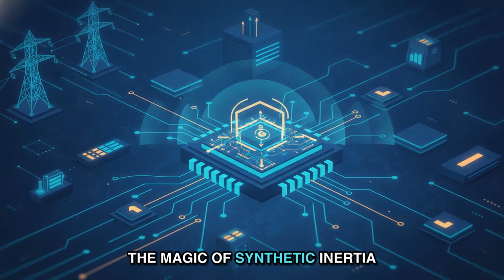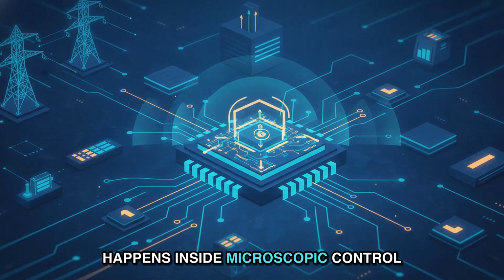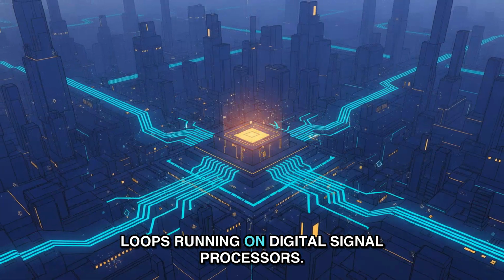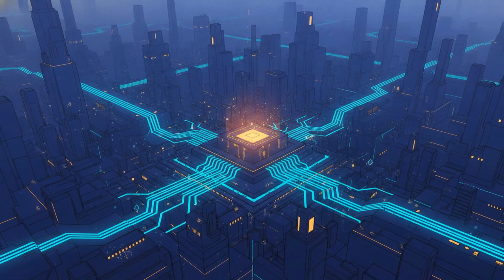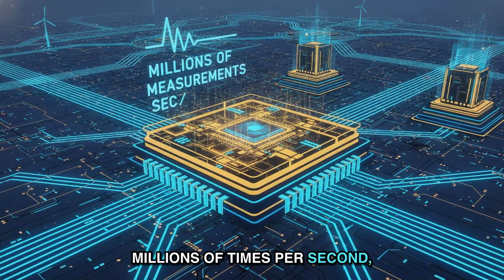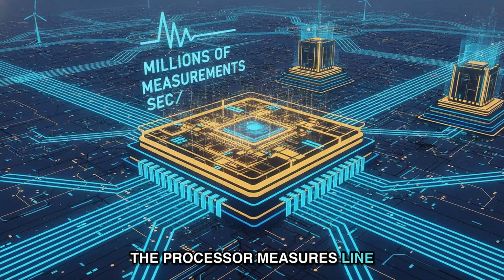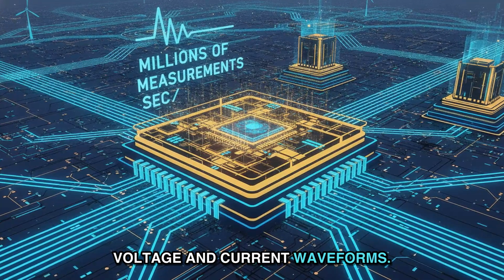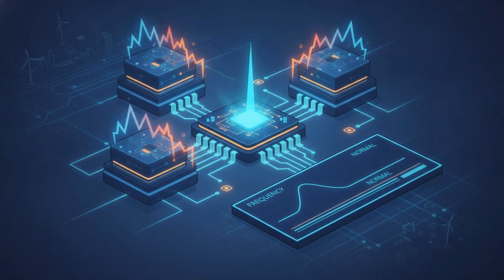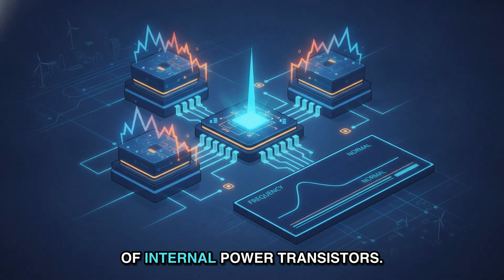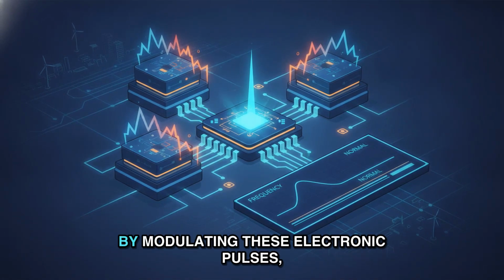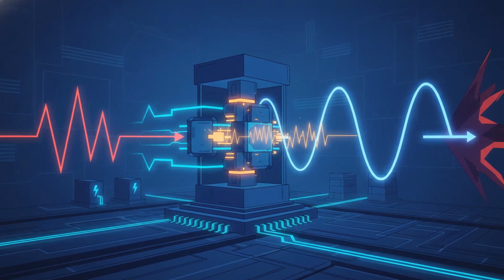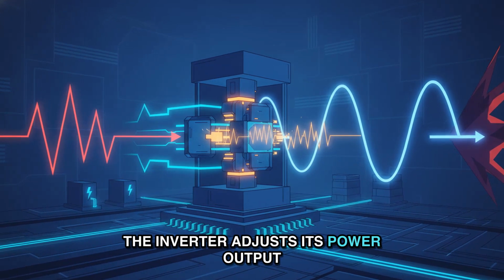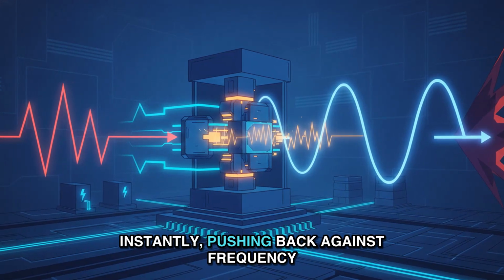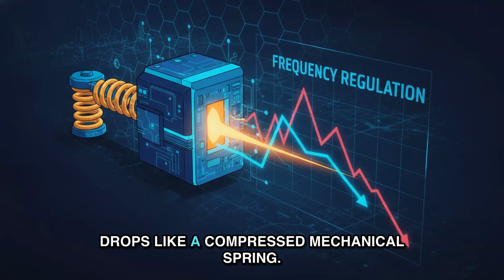The magic of synthetic inertia happens inside microscopic control loops running on digital signal processors. Millions of times per second, the processor measures line voltage and current waveforms. When it detects a disturbance, it adjusts the fast switching of internal power transistors. By modulating these electronic pulses, the inverter adjusts its power output instantly, pushing back against frequency drops like a compressed mechanical spring.